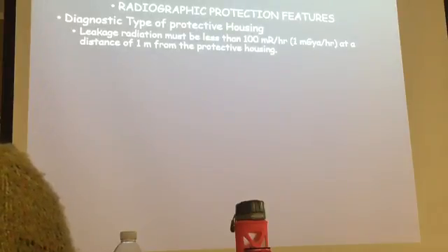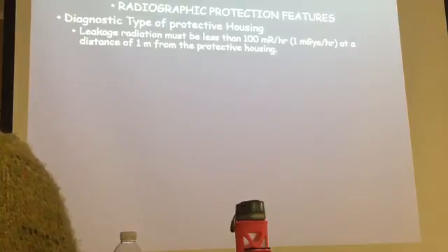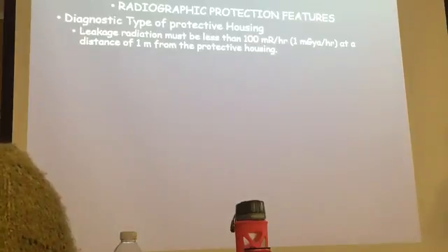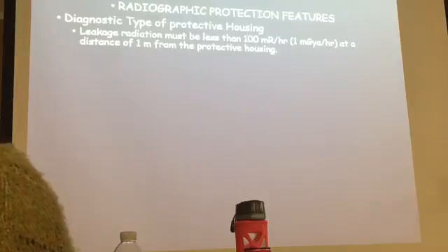And if you're thinking, well, don't you have just a beam coming out? No, remember that X-rays are created isotropically. We talked about it. What does isotropically mean? In all directions. So it is going everywhere, right? And even though we focus it on one area, and most of the X-rays come out that way because of the geometry of the X-ray tube, we want it to go in one direction. But you have X-rays going everywhere, okay? And so those of us working with it and the patient need to be protected.